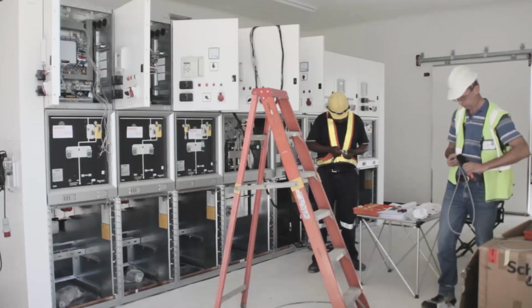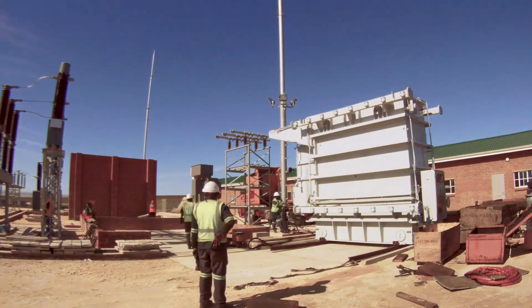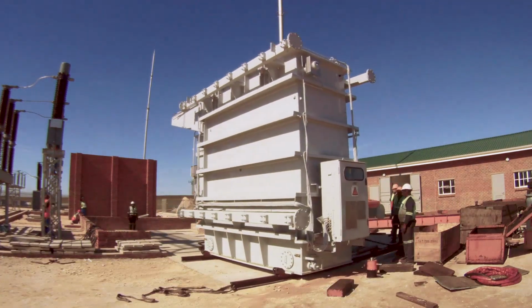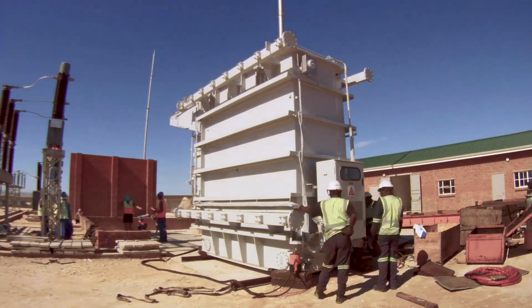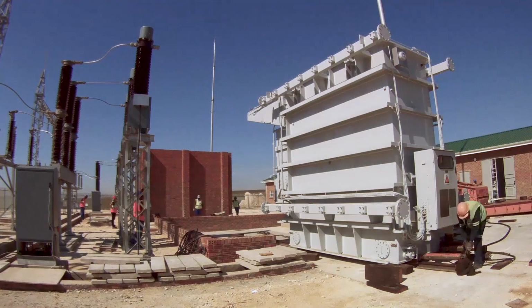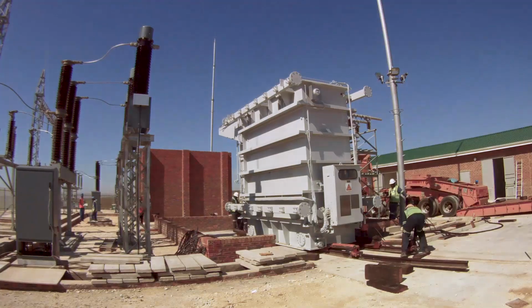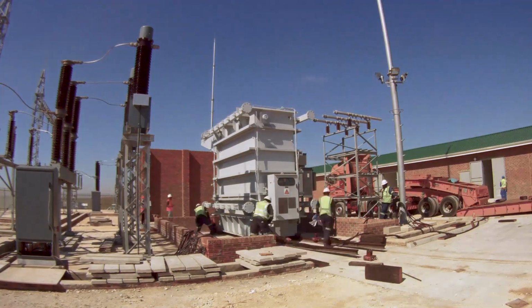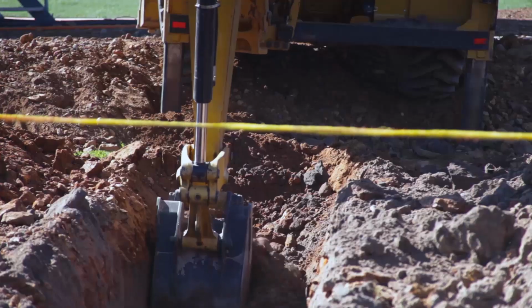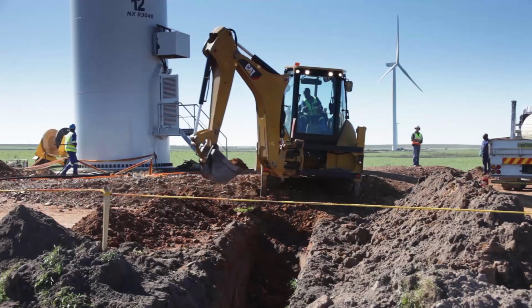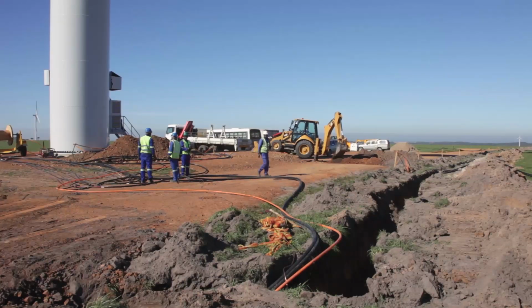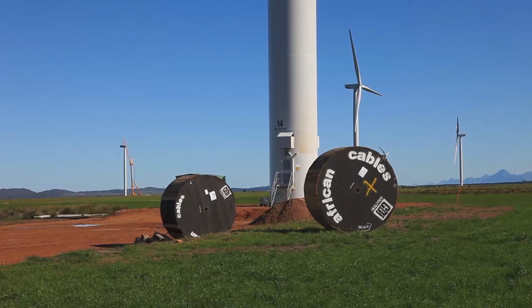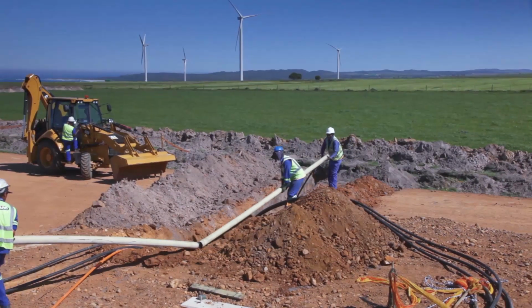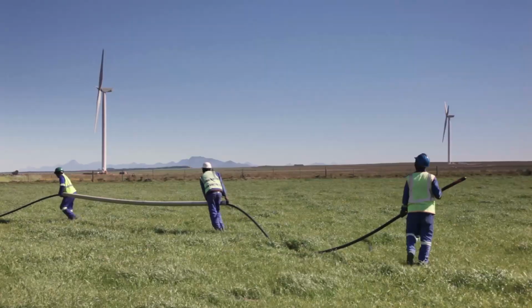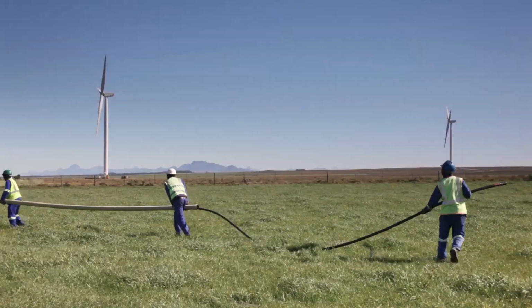The main components of the substation are the two main transformers. These increase the voltage of the power generated by the wind farm from 33 kilovolts to 132 kilovolts. Each wind turbine is connected to the next wind turbine and to the substation by means of medium voltage cables. These cables are buried in cable trenches that run alongside the roads of the wind farm. More than 150 kilometers of aluminum cable has been installed in approximately 30 kilometers of cable trenches.